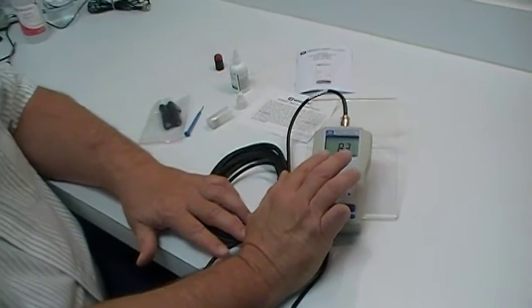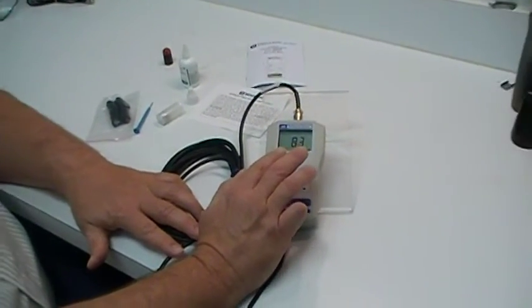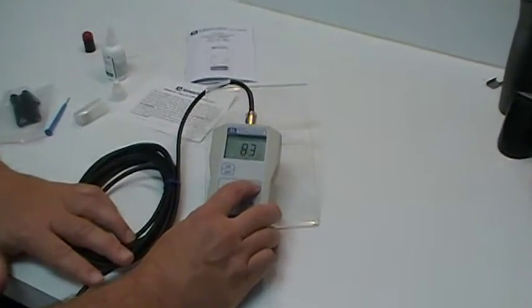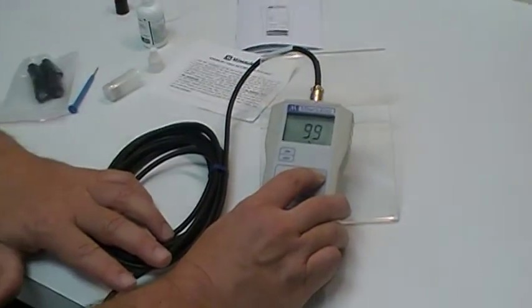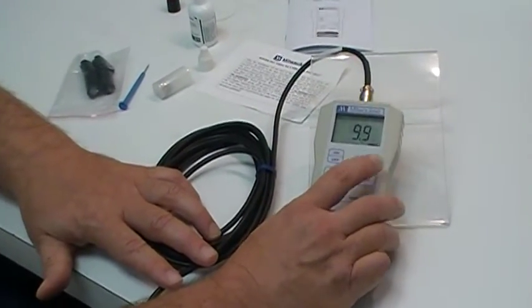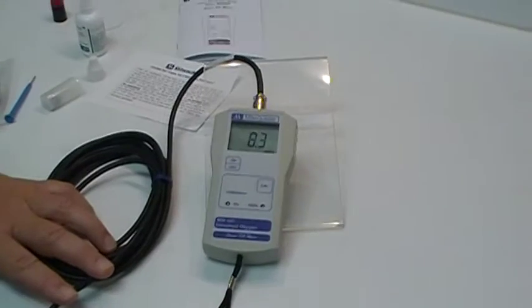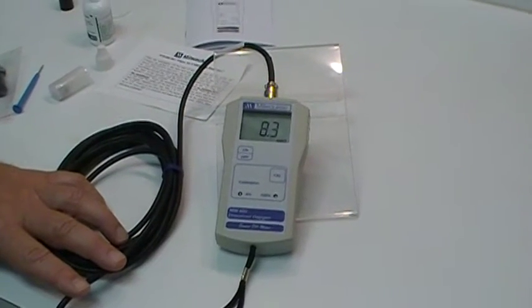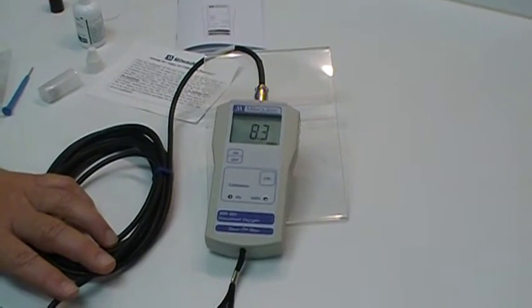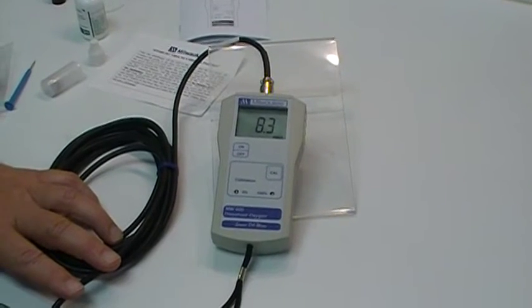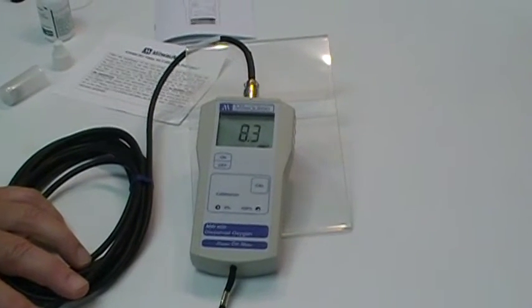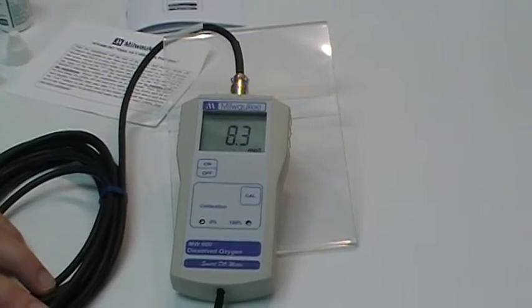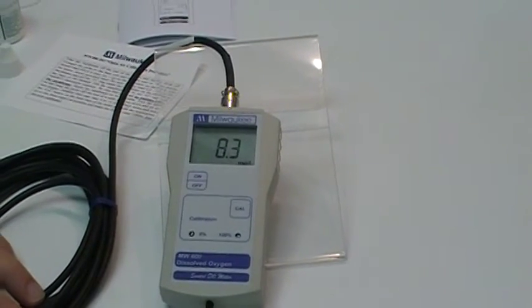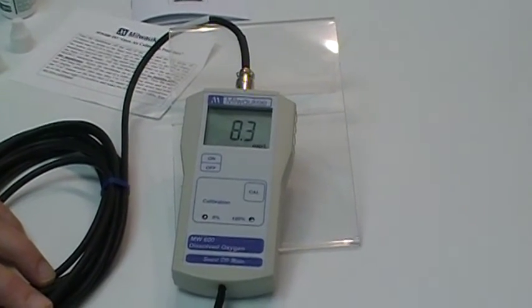As you see, it's dropping a little bit, and what's happening is that the electrolyte is being charged. If you press the number again, you notice that it's dropped from 100 down to 99. This is the reason why you would want to wait for 5 to 10 minutes for this unit to finally settle in before you do the 100%. So with that, that concludes the open air calibration procedure for the MW600 dissolved oxygen meter.